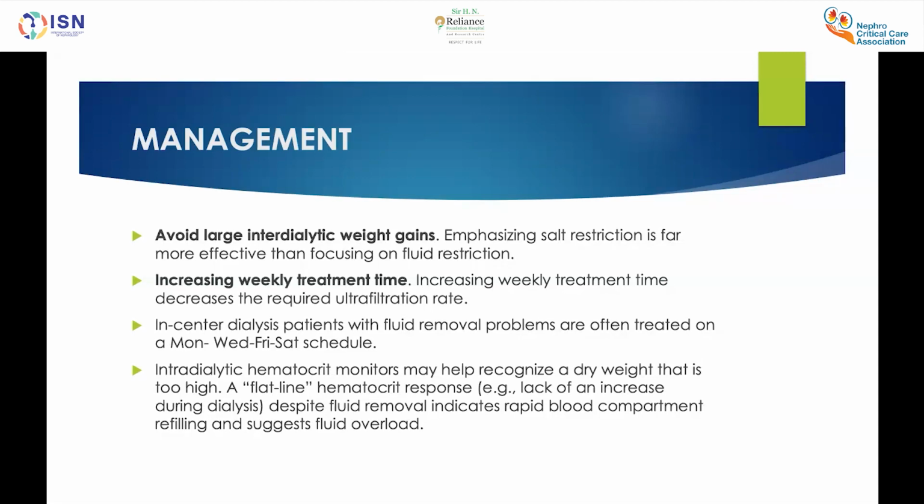Intradialytic hematocrit monitors may help recognize a dry weight that is too high. A flatline hematocrit response, despite the fluid removal, indicates rapid blood compartment refilling and suggests fluid overload.